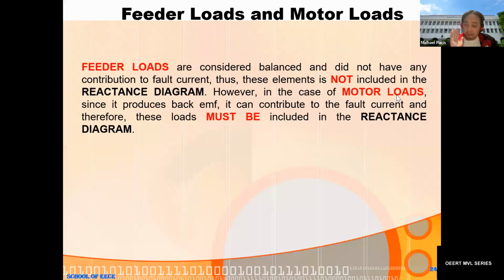But before we do that, please take note of the following: feeder loads are considered balanced, but they do not have a contribution to the fault current. Ito lang ang moral lesson dyan. If you see a feeder load, yung mga open-ended load, it does not have any contribution to the fault current, simply because the only contributors to the fault are those rotating machines, such as motor loads and your generators.